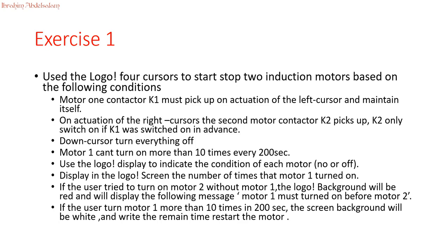Exercise 1: use LOGO! cursor keys to start and stop an induction motor based on the following conditions. Motor 1 contactor K1 must pick up on action of the left cursor and maintain itself. On action of the right cursor, the second motor contactor K2 picks up. K2 is only switched on if K1 was switched on in advance. Down cursor turns everything off.